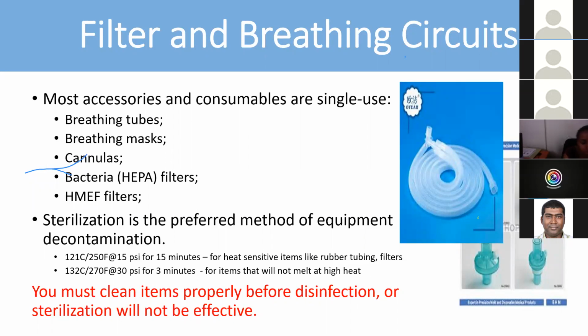So basically, when you talk about certain breathing circuits that are reusable, they're going to use a sterilization method. Okay, that's a temperature of 121 degrees at 15 psi for 15 minutes for heat-sensitive items like rubber and tubing filter, and 132 Celsius for 3 minutes for items that will not melt in high heat. Most of these breathing circuits have a mark on the circuit that shows the temperature you can sterilize at. All the details are there normally.